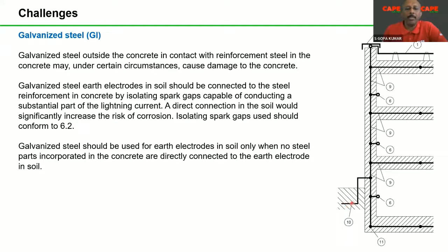So for example, what it says is, if you wanted to connect, you have a natural component used as down conductor, and you have to connect to something which is in soil, and that something is galvanized. Don't connect directly is the recommendation. You put a spark gap in between. So electrical isolation or spark gap is necessary. So these recommendations are there in soil.